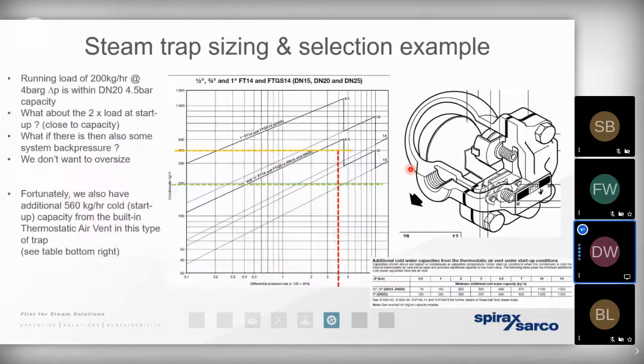So every steam trap type has got its own sizing curve. If you look at the red line that we've identified here, the red line that runs vertically upwards, that's representative of that 4 bar gauge differential pressure that we've spoken about. The green line is the 200 kilograms per hour condensate load that we've spoken about. So when the two intersect, that shows us how we select the appropriate steam trap type. But remember, we've got that running load as well as the warming up load we need to contend with. So the green line represents the running load. The orange line represents the warming up load. In other words, we've doubled the running load.